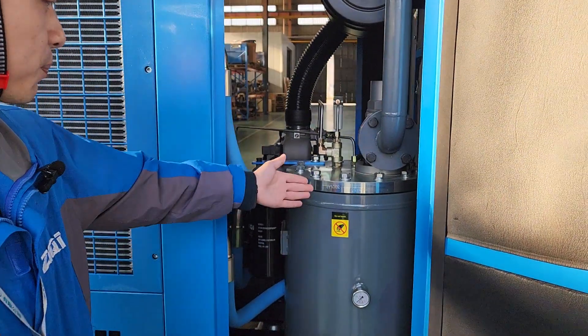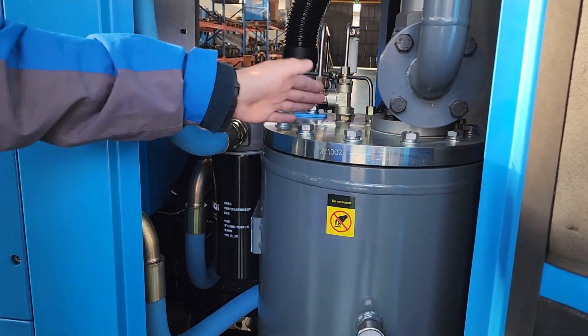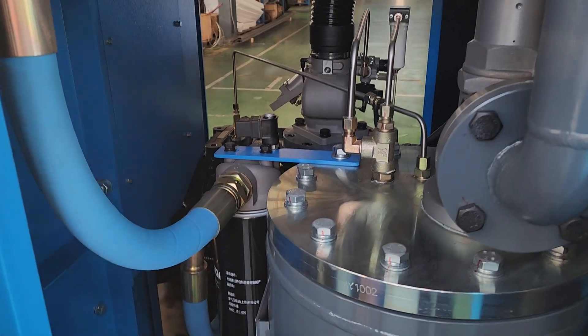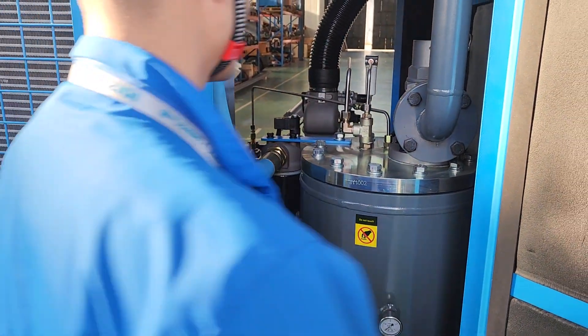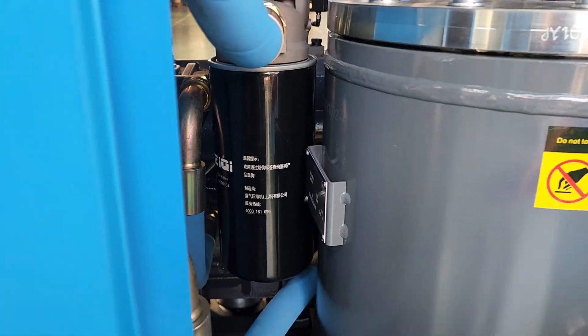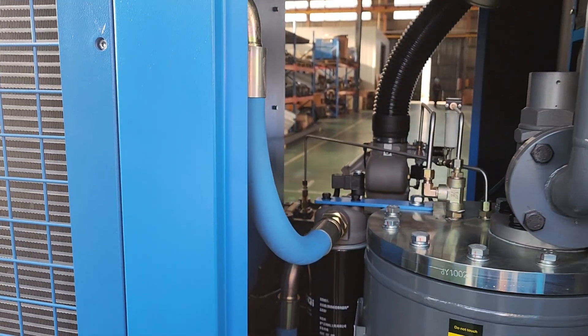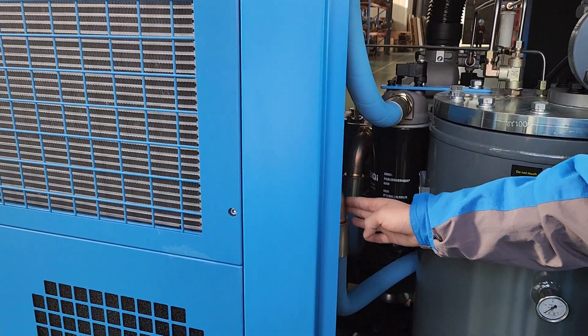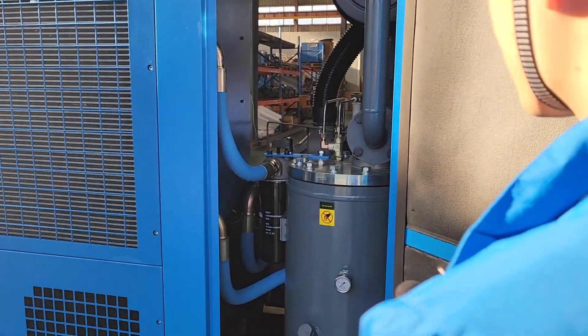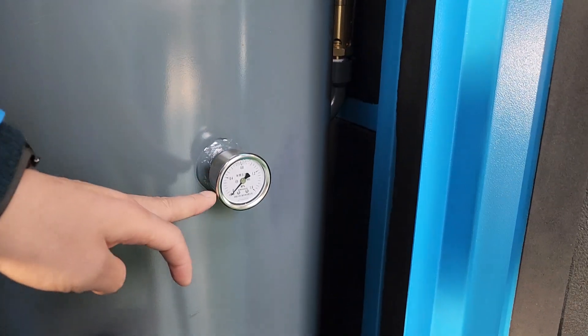You can see here is a bigger-size oil-air separator with higher efficiency to separate the compressed air and lubrication oil. The filter adopts a Germany brand with small pressure loss. Here is the oil filter. As for the oil tubing, Zichi Compressor uses the Italian brand hose — the service life is over five times longer than ordinary — and with Zichi's unique connector to ensure 100% non-oil leakage. The oil-air separator is also equipped with a safety valve, pressure gauge, and oil sight glass.